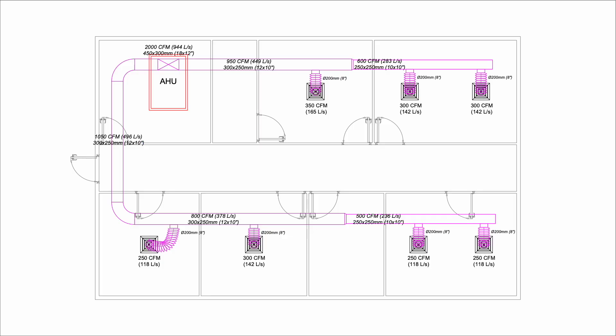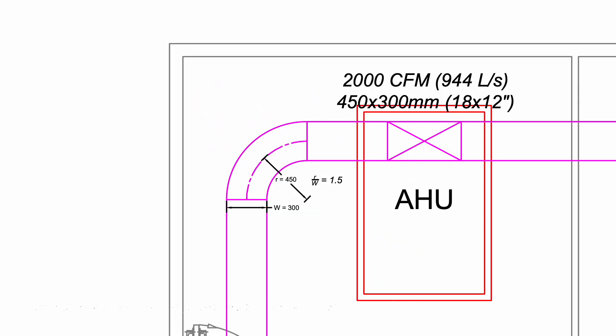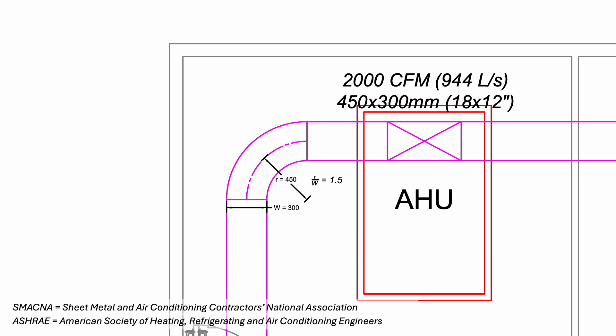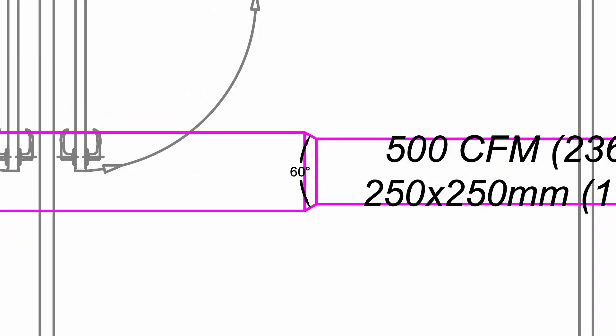Once we have all the supply duct sizes, we can go ahead and draw the duct to scale. Based on SMACNA duct construction standard, the elbow radius to duct width ratio should be 1.5. Tighter elbows such as 1.0 ratio are also acceptable as HVAC software does provide the database to calculate the pressure drop. As for duct transitions, it should be 60 degrees for reducers and 45 degrees for enlargers.